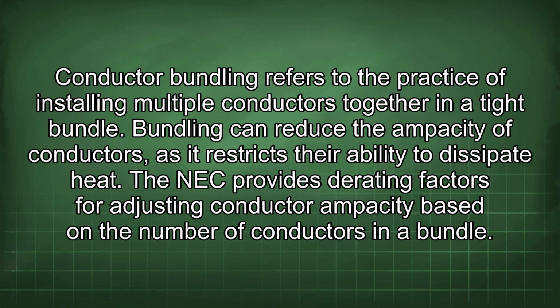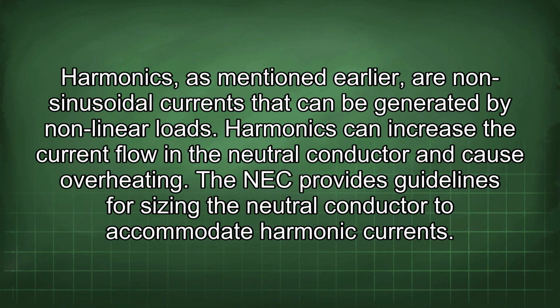Conductor bundling refers to the practice of installing multiple conductors together in a tight bundle. Bundling can reduce the ampacity of conductors, as it restricts their ability to dissipate heat. The NEC provides derating factors for adjusting conductor ampacity based on the number of conductors in a bundle. Harmonics, as mentioned earlier, are non-sinusoidal currents that can be generated by nonlinear loads. Harmonics can increase the current flow in the neutral conductor and cause overheating. The NEC provides guidelines for sizing the neutral conductor to accommodate harmonic currents.